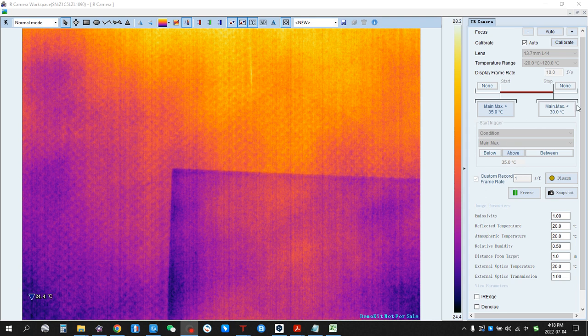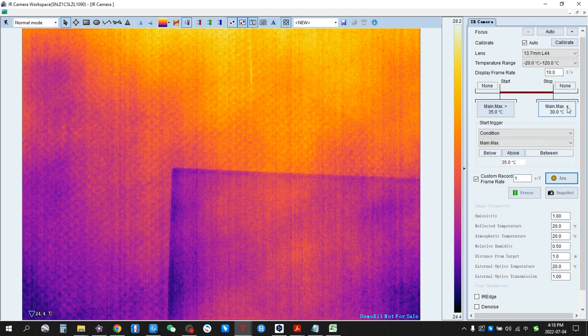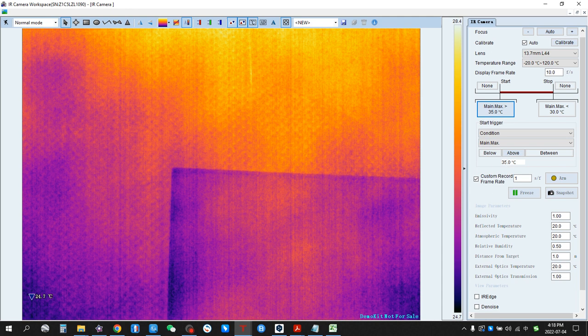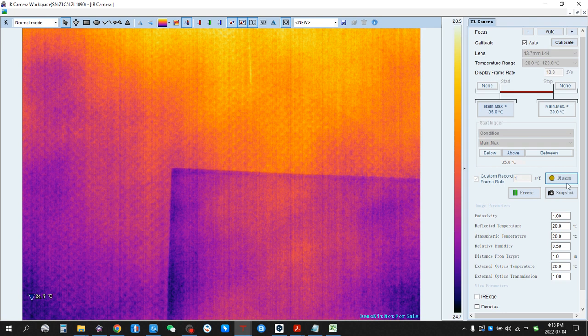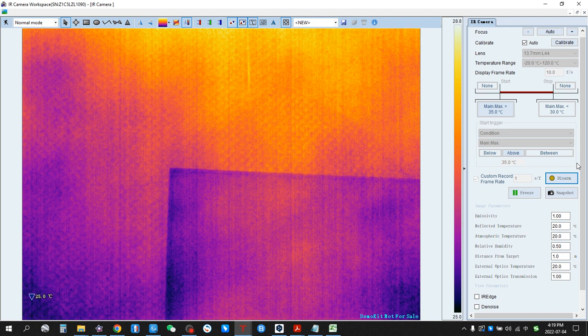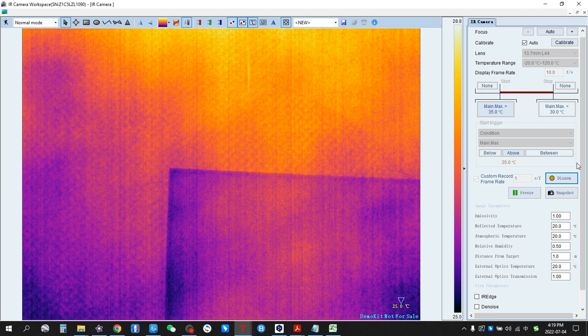We can also set a trigger for stop. We can set 30 degrees — below 30 degrees as a trigger to stop. For the start trigger, we can set about 35 degrees. That means when the temperature detected is over 35 degrees Celsius, the camera will record automatically. If the maximum temperature detected is below 30 degrees Celsius, the recording will stop automatically.